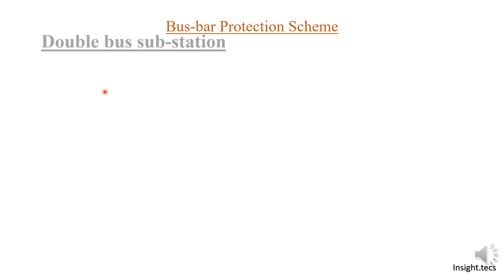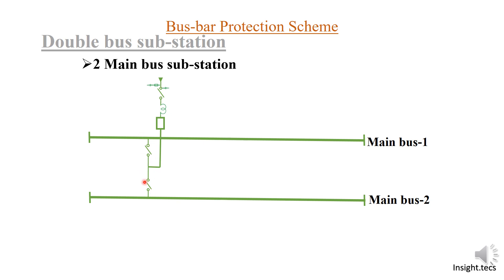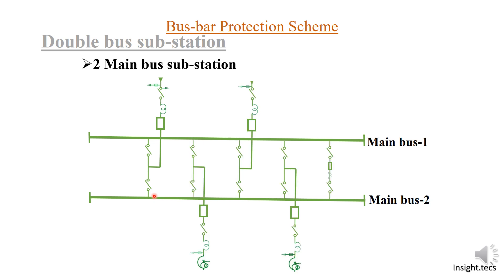Now, the double bus substation — also called the two main bus substation — has Bus 1 and Main Bus 2 with a feeder arrangement. Selector isolators are provided that help you select Bus 1 or Bus 2, similarly for the transformers as well. For the two bus substation the main component is the bus coupler, which connects the two buses.